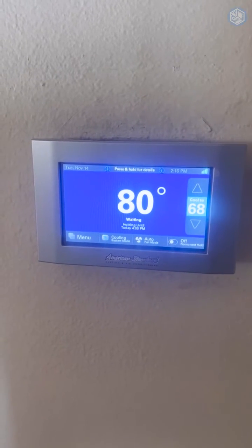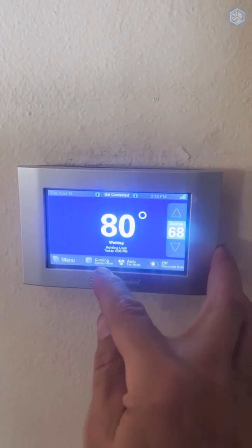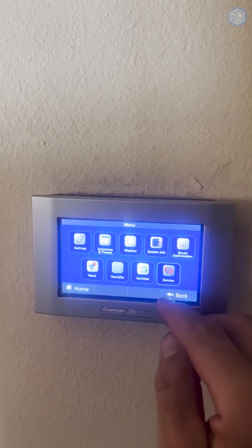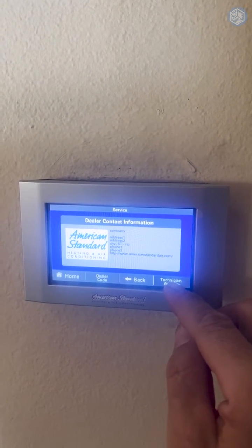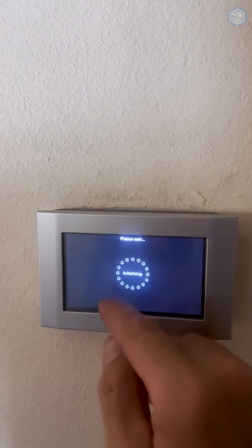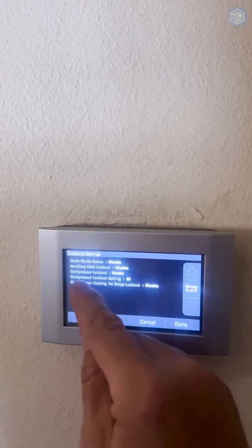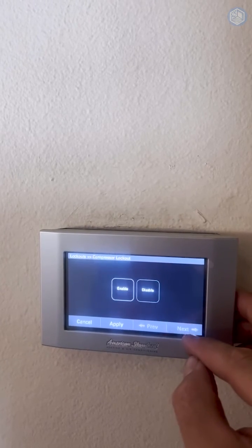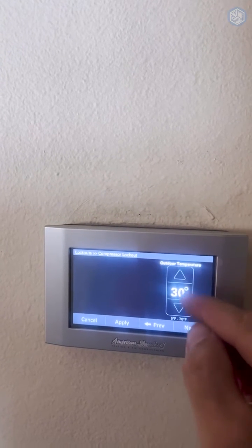How to choose dual fuel heat pump mode with American Standard? Choose what heat source you want to use. Go to menu, go to service, hold the technician access button for 10 seconds, proceed, then installer setup, and go to page number six. You have a compressor lockout setting — click edit, next, next, compressor lockout, and that sets outdoor temperature.